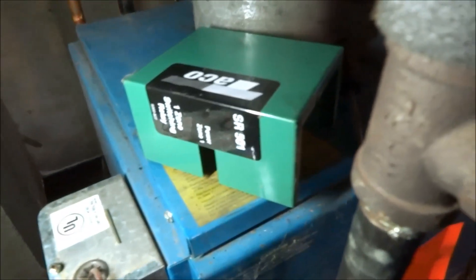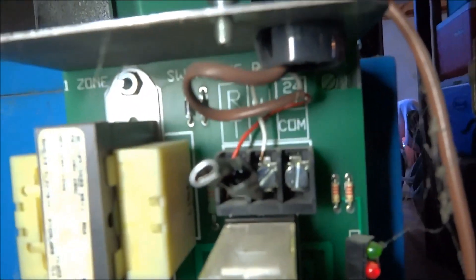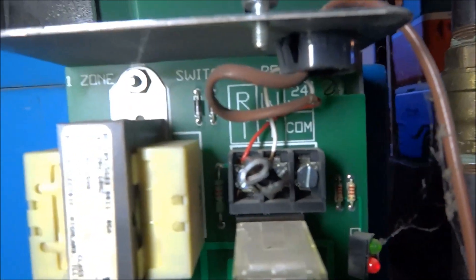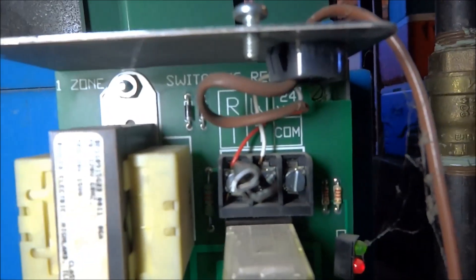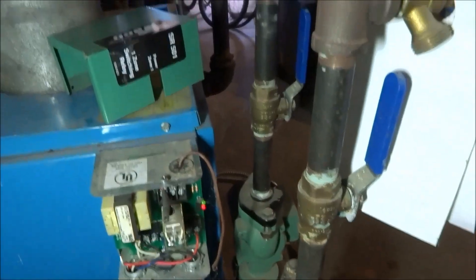Alright guys, I got zone one cover off. The thermostat jumped out, I believe he has them off, I don't know why. I just want to make sure both zones are coming back hot, which they are. Both returns are coming back hot, so there's no freeze up.